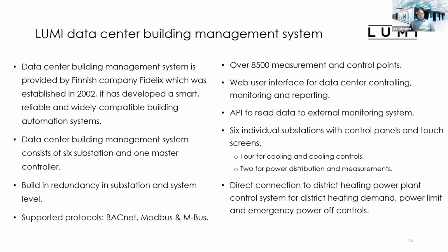Those 6 individual substations are installed on the first floor of the data center, and all of them have local control panels and touch screens, so we can operate the building management system locally from the data center itself in case of any issue. There are 4 of these substations for cooling and cooling controls, and 2 are for power distribution and power measurements.